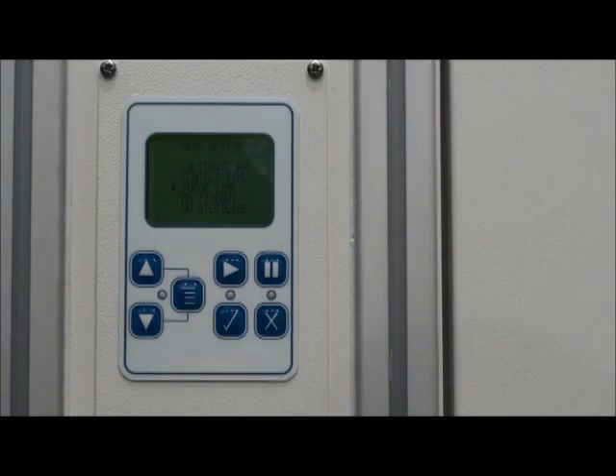Next comes the purge time. The purge is what cuts in after the vaporization period to extract the fumes from the chamber. So you press the tick to accept entry to the menu, and at the moment that displays 10 minutes. You can set that for a time of your own choice. We recommend between 15 and 20 minutes. To accept that time, you press the tick.